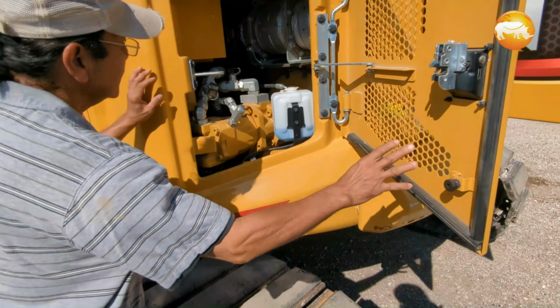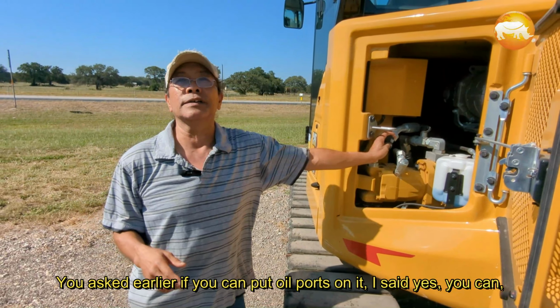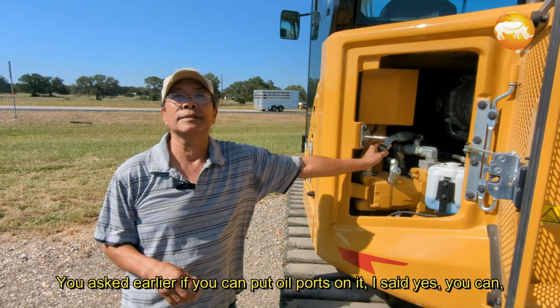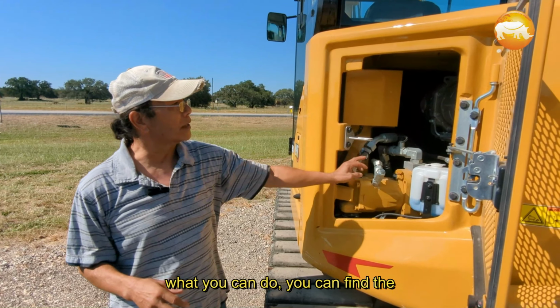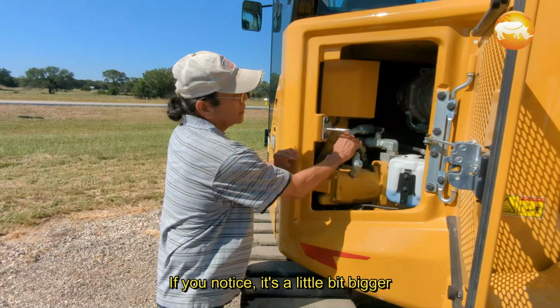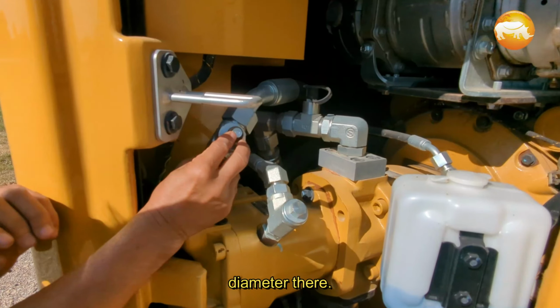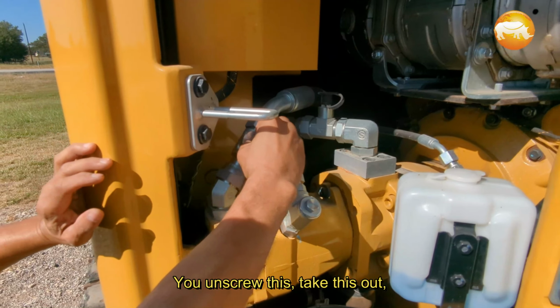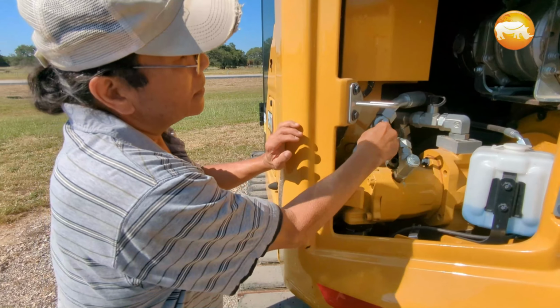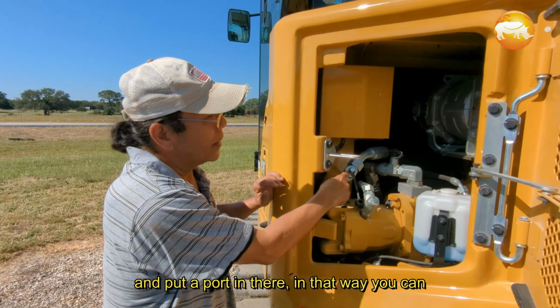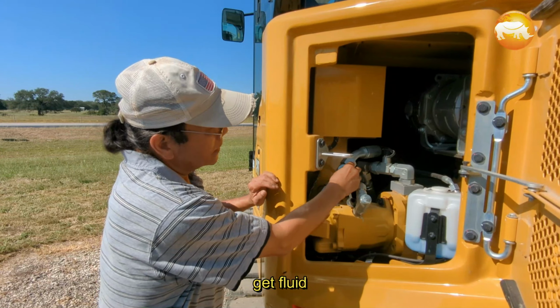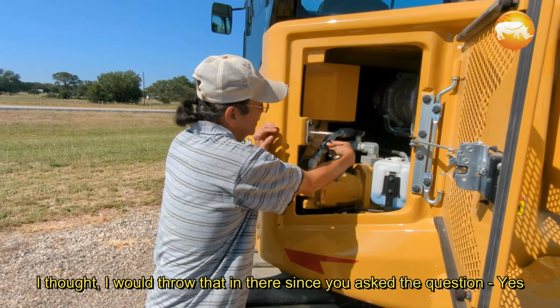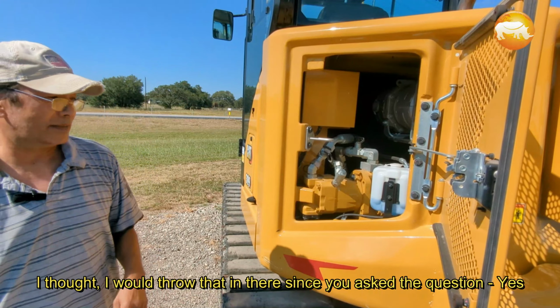Okay, I'm going to throw this in. You asked earlier if you can put oil ports in there, and I said yes you can. What you can do is find a pressure testing port, which, if you notice, is a little bit bigger in diameter. You unscrew this, take this out, and put a port in there, and that way you can get fluid for your pump. Not just your hydraulics, but it'll also pull fluid out of that pump. Perfect. Even better test. Thought I'd throw that in there because you asked that question.